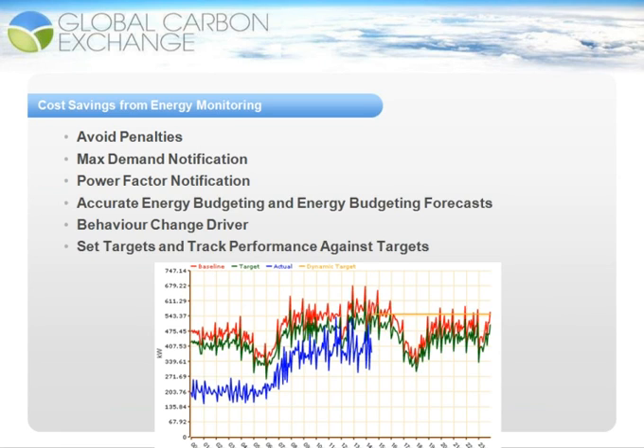Maximum demand notification is very useful not only in industrial facilities but also in commercial facilities with large air conditioning plants running. By setting maximum demand thresholds in your energy monitoring system, you can avoid reaching a specified level of maximum demand and thereby reduce your maximum demand charges for the month.